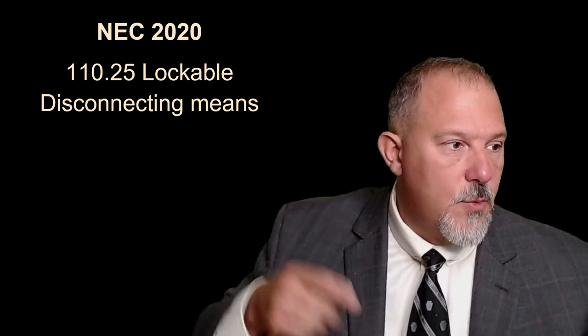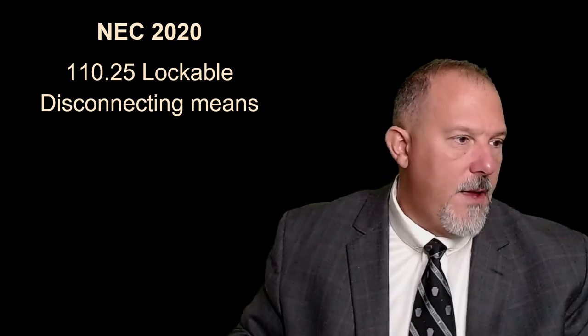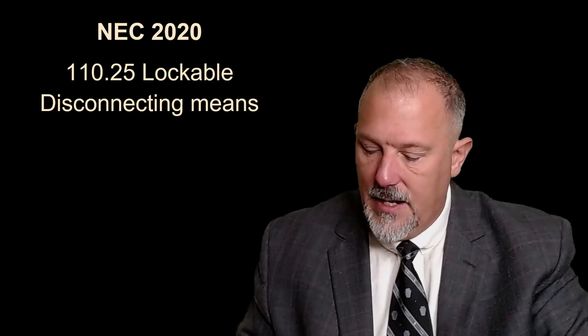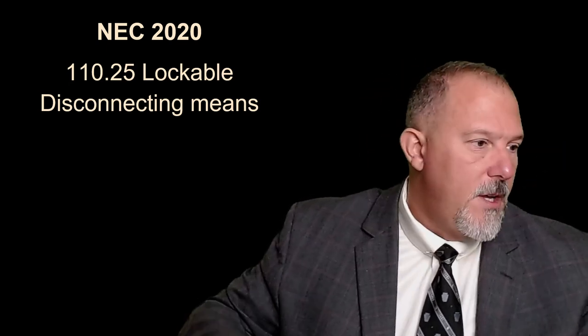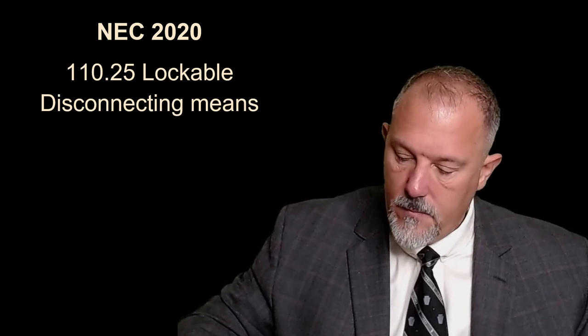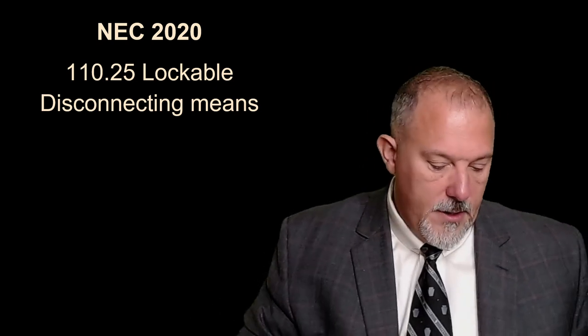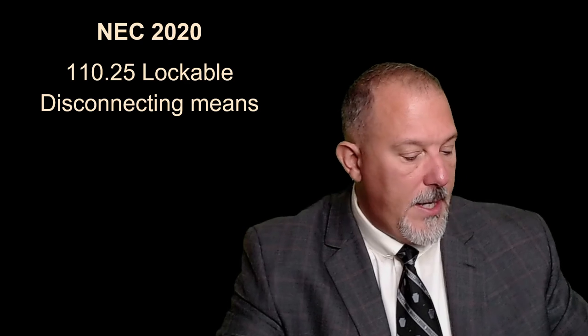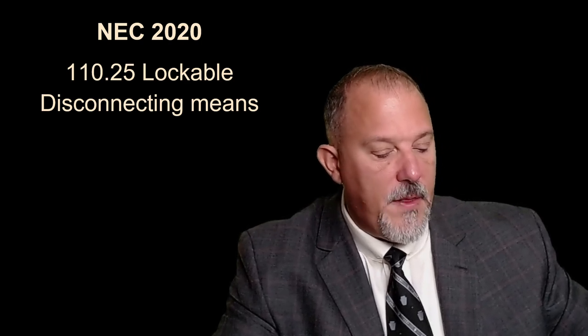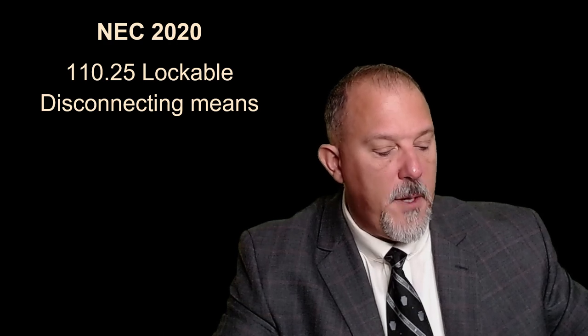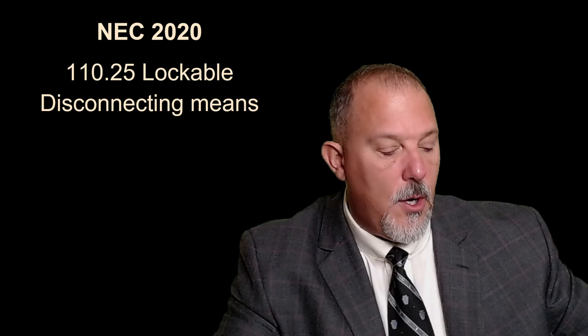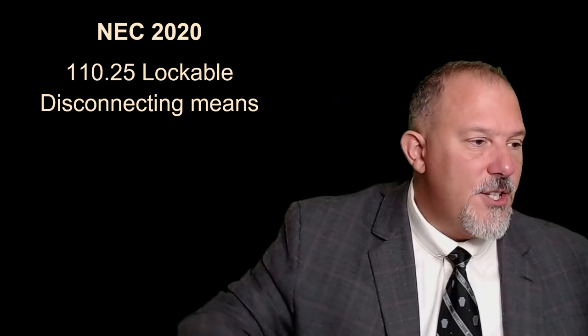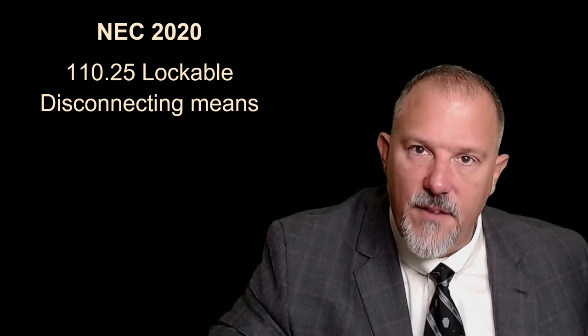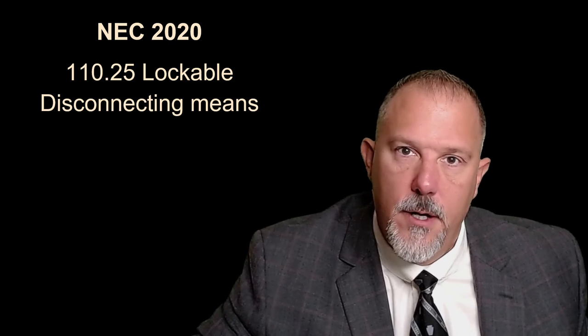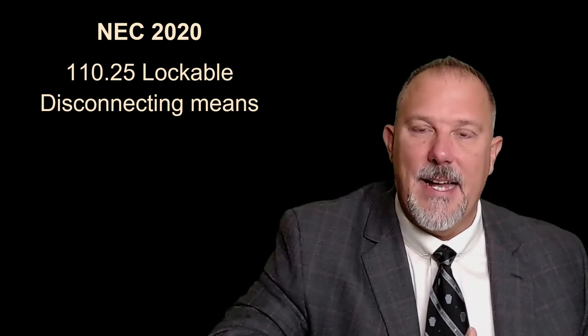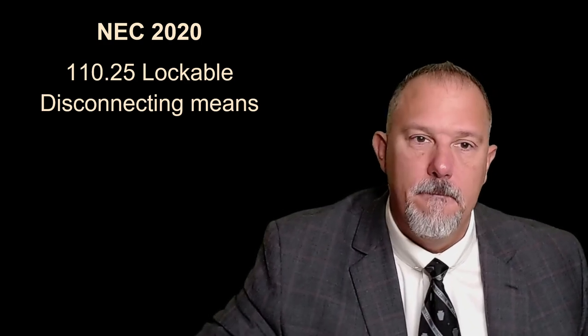There are various locations within the National Electrical Code where there are provisions. So one of them, Article 410, I believe that's in lighting, right? Luminaires, lamp holders, and lamps. 410.141. Let's go to 410.141. This is just one example. If we go to B, the switch or circuit breaker shall be located within sight from the luminaires or lamps, or it shall be permitted to be located elsewhere if it is lockable open in accordance with 110.25. If you just did a search in the National Electrical Code for 110.25 references, you would find a boatload of requirements to install a disconnect that is able to be lockable in the open position.